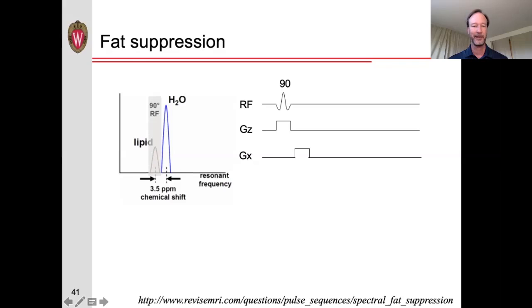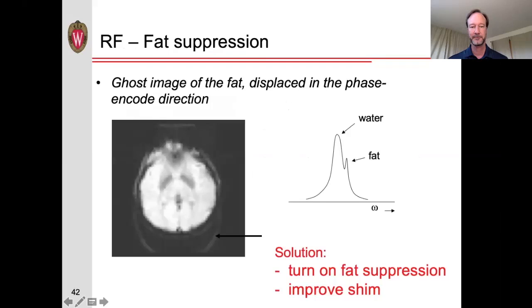Now, what effect that has is, remember, with MRI, we're trying to use the frequency of the spins as the position. We're using gradients to encode the frequencies. And so, as you can see here in this image, the fact that it's actually resonating at a different frequency causes a ghost of this object displaced a little bit.